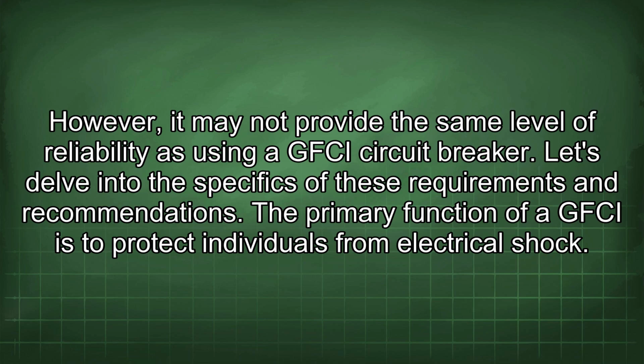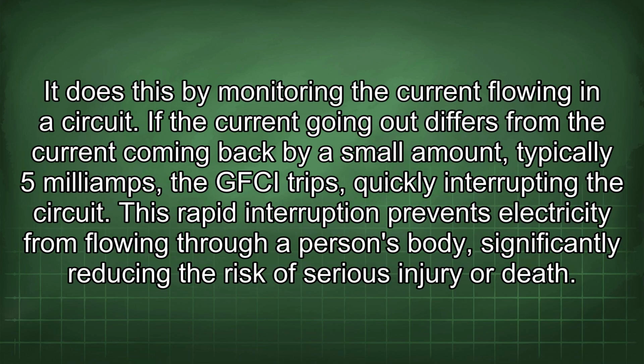The primary function of a GFCI is to protect individuals from electrical shock. It does this by monitoring the current flowing in a circuit. If the current going out differs from the current coming back by a small amount, typically 5 mA, the GFCI trips, quickly interrupting the circuit. This rapid interruption prevents electricity from flowing through a person's body, significantly reducing the risk of serious injury or death.